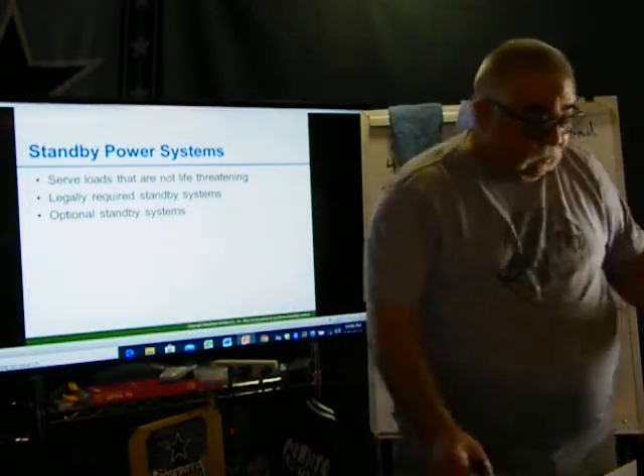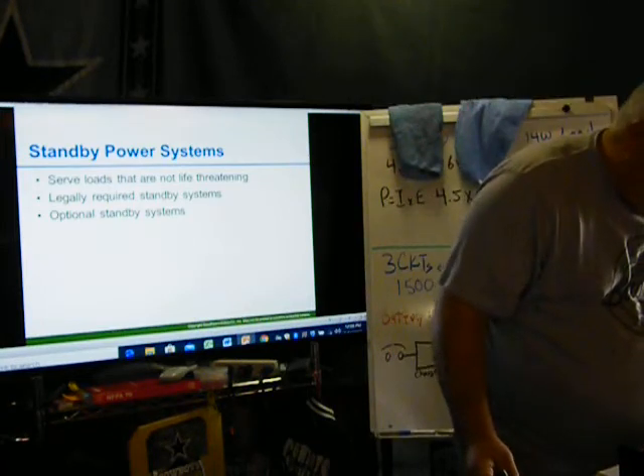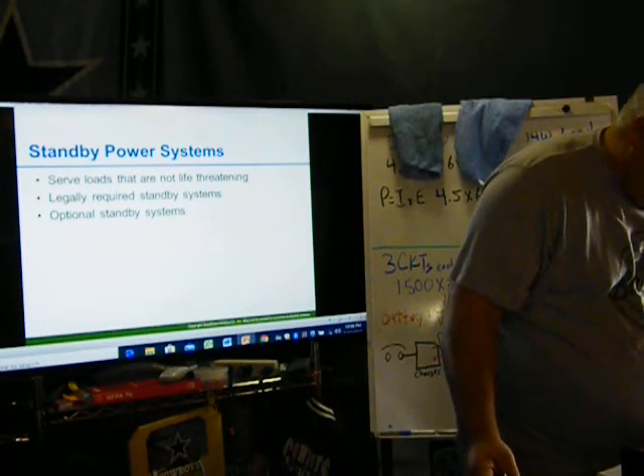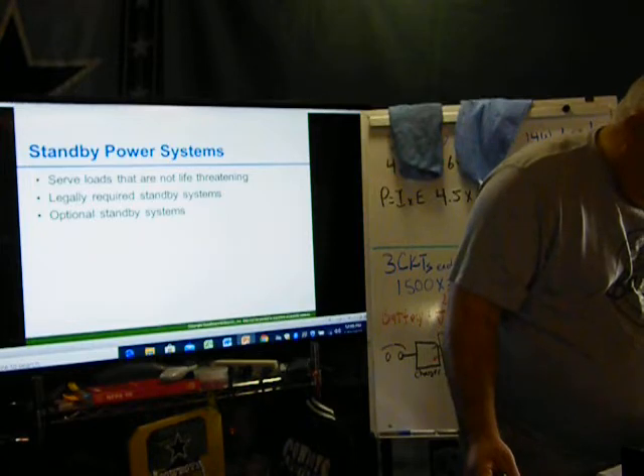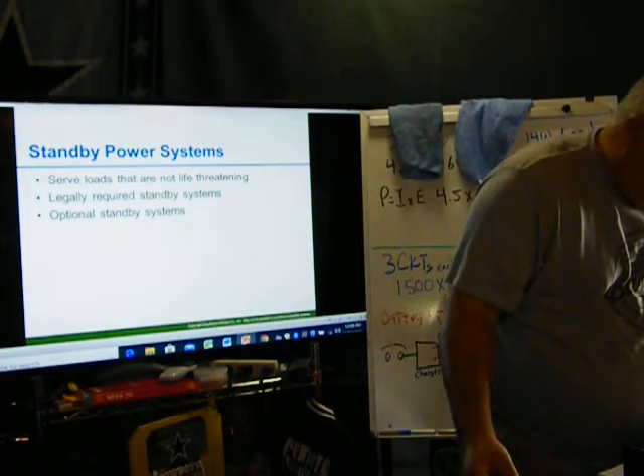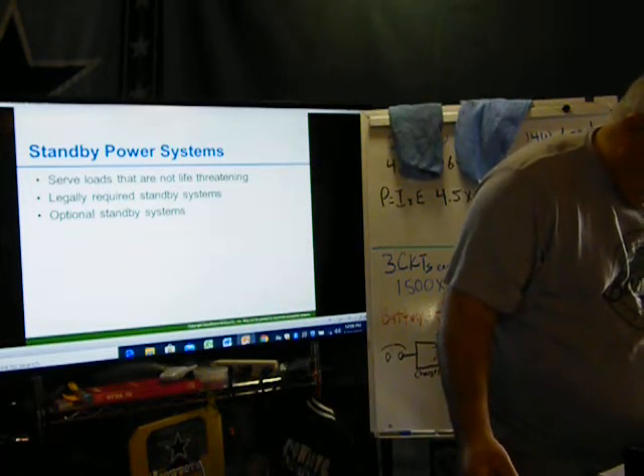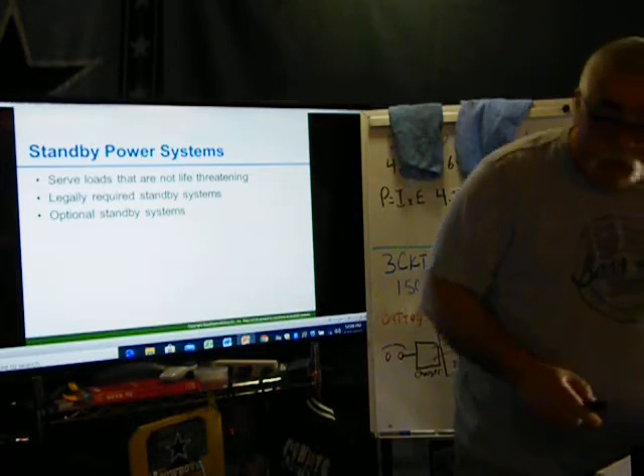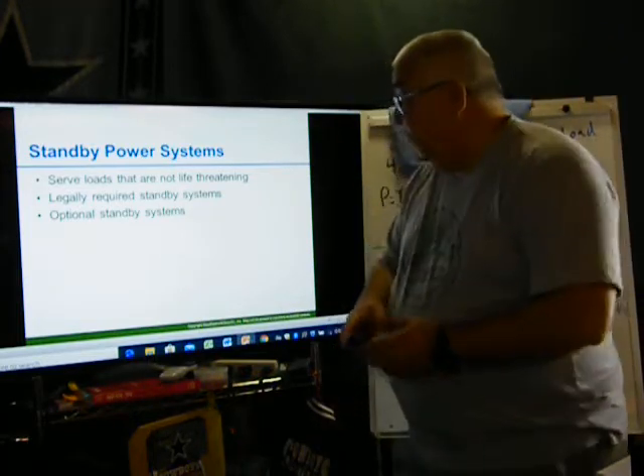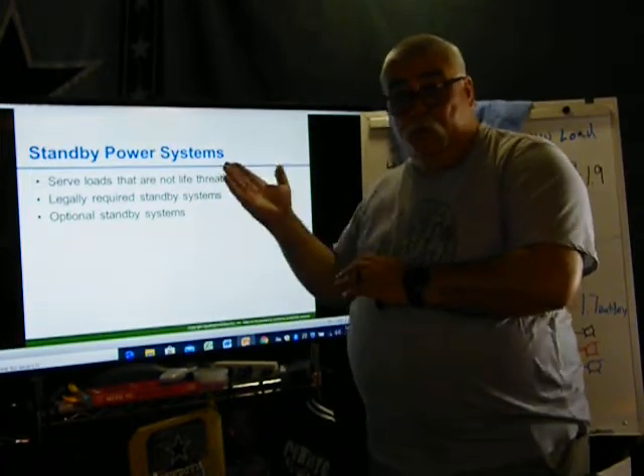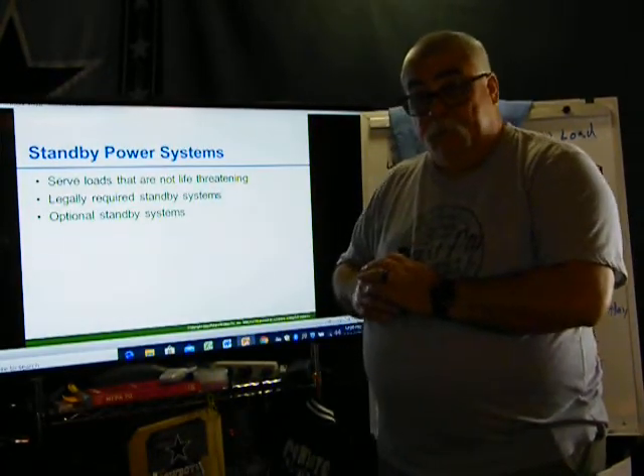Standby power systems. A standby power system serves loads that are not life-threatening in the event of a power failure. The code recognizes two types of standby systems: the legally required and the optional. The transfer of power from the normal source to the emergency source must be automatic for legally required standby. For optional standby systems, the transfer may be automatic. Okay, so if I have a legally required system, I got to have an automatic transfer switch. Turns on and off. Okay, what's legally required?